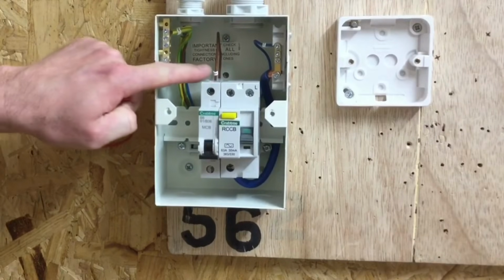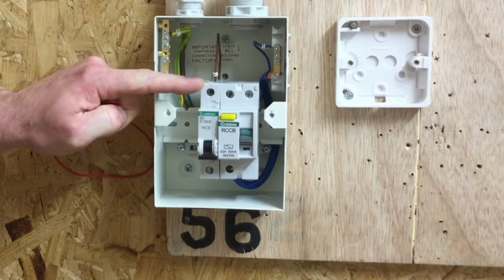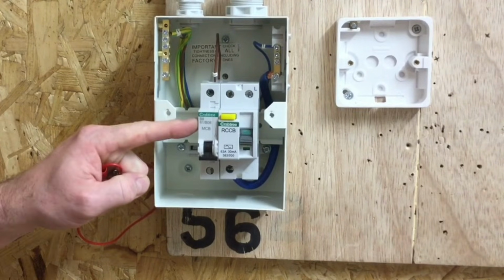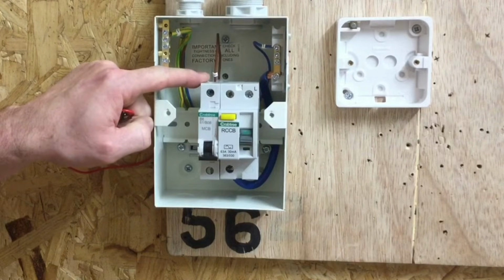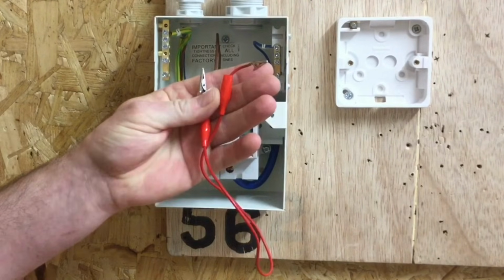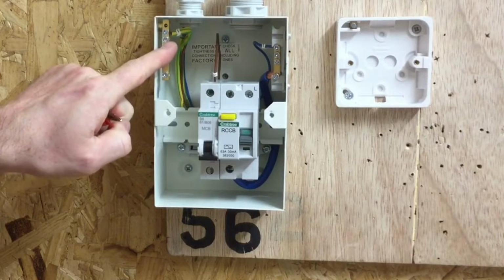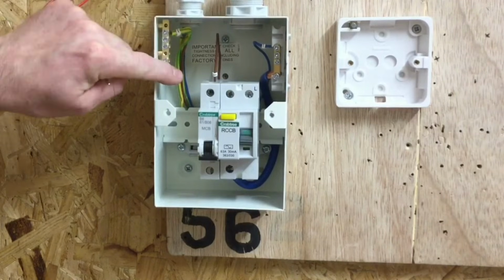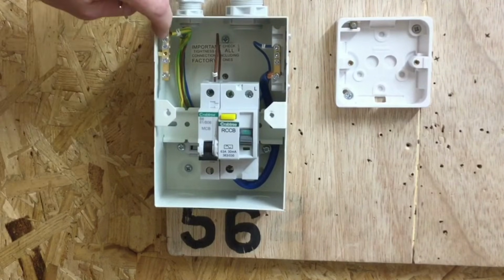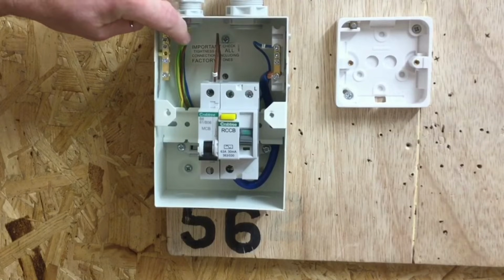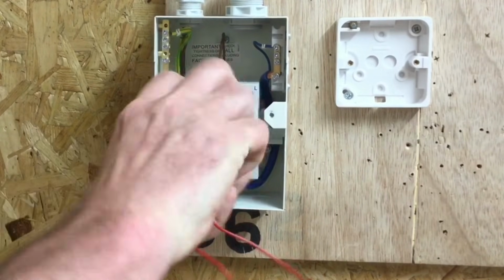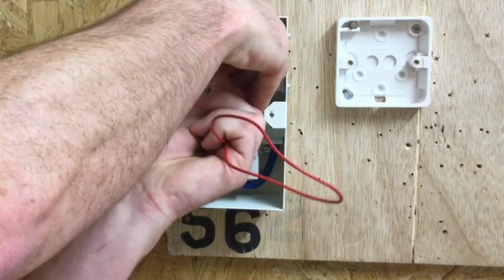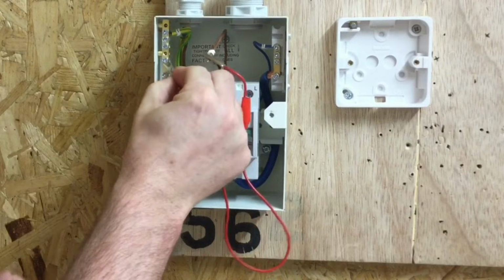So first of all, I'm going to remove the line conductor out the top of the circuit breaker for the circuit that is under test. I've only got one circuit here, so for my B6, for my lighting circuit, I'm just going to disconnect my line conductor. Then I'm going to use my crocodile clips to link the disconnected line conductor to the earth bar. It doesn't matter where the crocodile clip goes. This is a solid brass bar, so we can clip anywhere on it. We don't have to clip directly on top of the screw to the CPC that we've got. Let's disconnect my line conductor and I'm going to connect it to the earth bar.